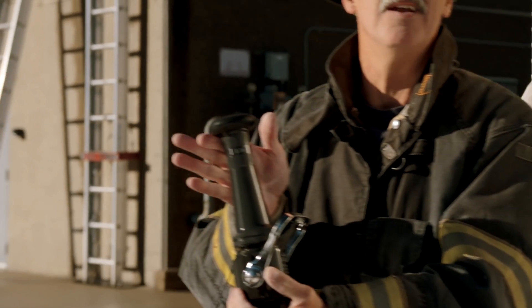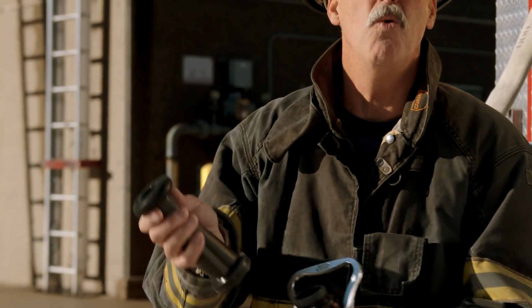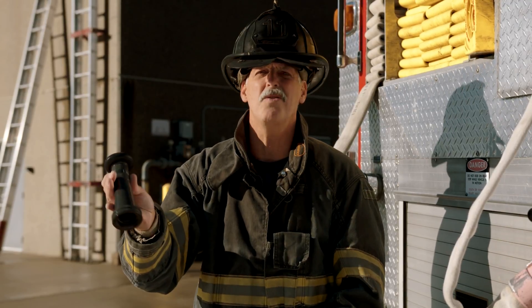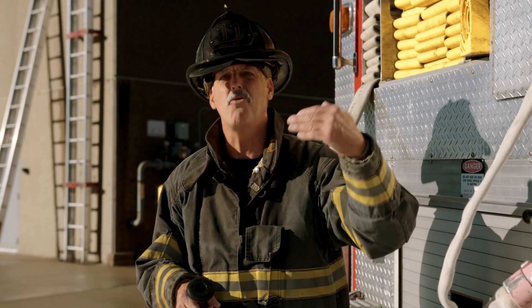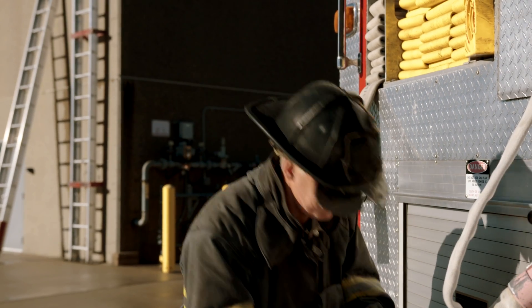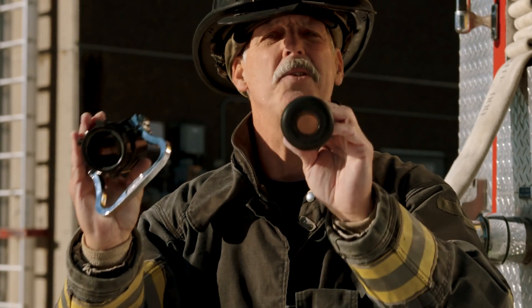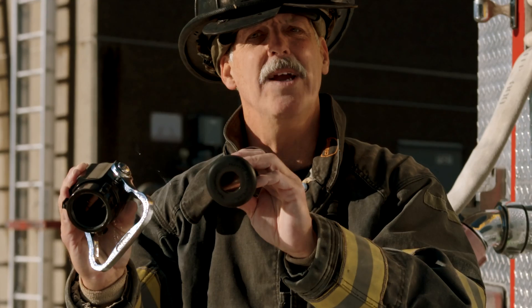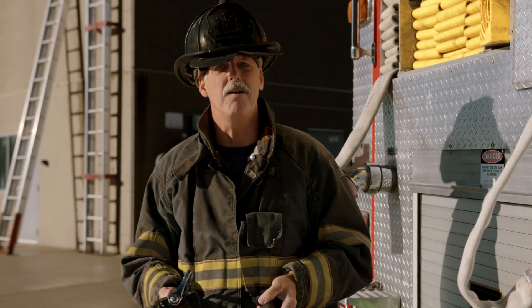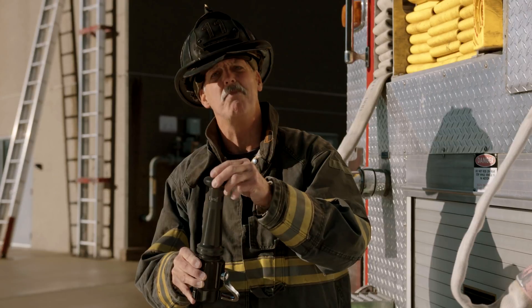This is a 1-1/16-inch nozzle right here. Old hydraulics formulas would say that a solid tip should never exceed 50% of the hose's diameter — well, this is 1-1/16 on a two-inch line. With the materials used in the construction of the hose and greater flows, we now have an inch-and-three-eighths waterway coupled with a 1-1/16-inch tip, and we're able to get substantial flows — consistently in the 240 to 260 gallon-per-minute range. That's a bigger bang for the buck, especially for fire departments concerned about GPM output for the number of firefighters responding on an engine.